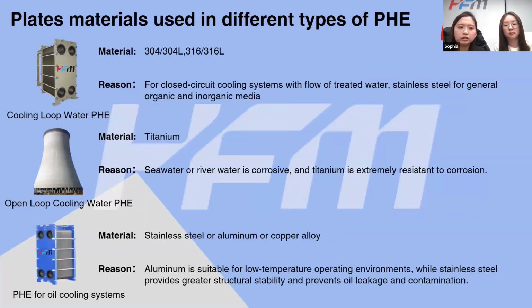So on this page, we show the plate materials used in different types of plate heat exchangers. The first, the cooling loop water plate heat exchanger, uses 304 or 304L and 316 or 316L stainless steel as the material. This type of plate heat exchanger is mainly used for closed circuit cooling systems with flow of treated water, and is for general organic and inorganic media. The use of stainless steel ensures that the heat exchanger maintains good corrosion resistance and stability under a wide range of cooling conditions.